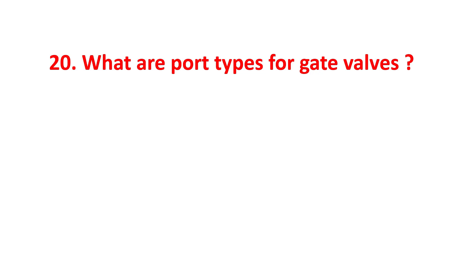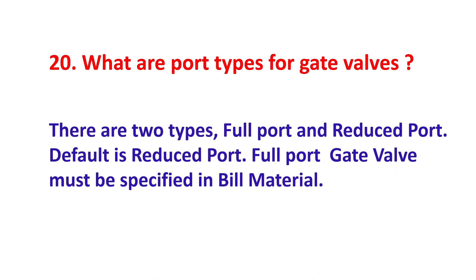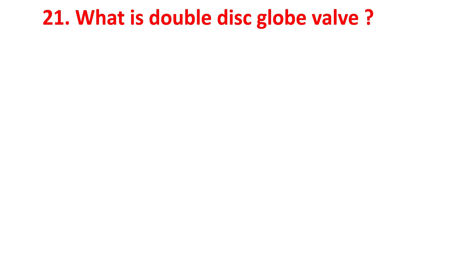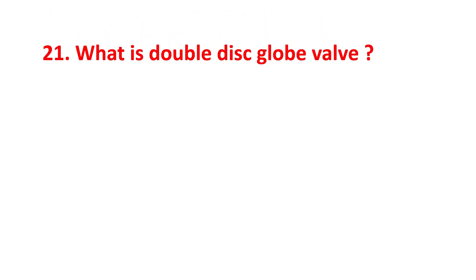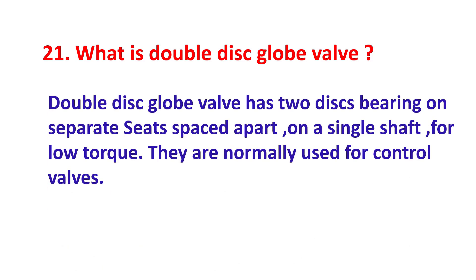What are port types for gate valves? There are two types: full port and reduced port. The default is reduced port. Full port gate valves must be specified in bill of materials. What is a double disc globe valve? A double disc globe valve has two discs bearing on separate seats spaced apart on a single stem. They are used for low torque control valves.